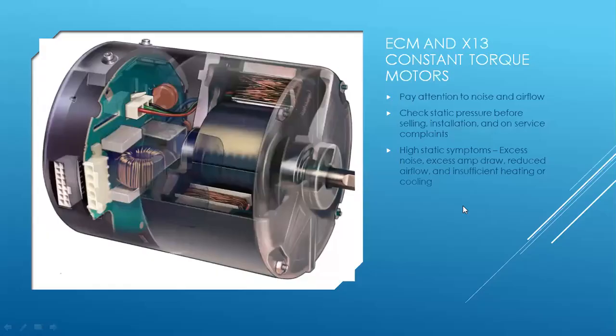Okay, so yeah, pay attention to noise and airflow. With both ECMs and X13s, if you run them under extreme static pressure, you will burn them out, guaranteed. Used to have guys that were on their third and fourth X13 motor, and they're like, well, these motors are junk. It's not the motors that are junk. It's the condition that they're running at. So if you run them hard enough, you will blow that little resistor in the end plate.